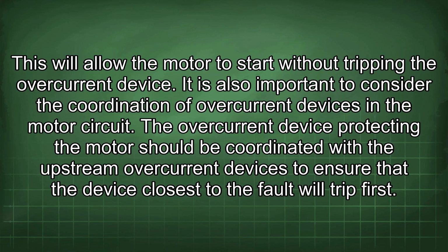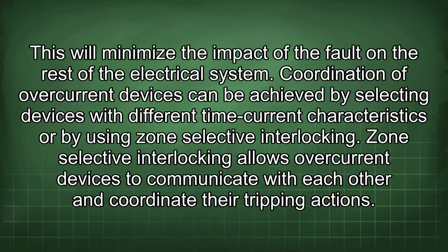It is also important to consider the coordination of overcurrent devices in the motor circuit. The overcurrent device protecting the motor should be coordinated with the upstream overcurrent devices to ensure that the device closest to the fault will trip first. This will minimize the impact of the fault on the rest of the electrical system. Coordination of overcurrent devices can be achieved by selecting devices with different time current characteristics or by using zone selective interlocking. Zone selective interlocking allows overcurrent devices to communicate with each other and coordinate their tripping actions.